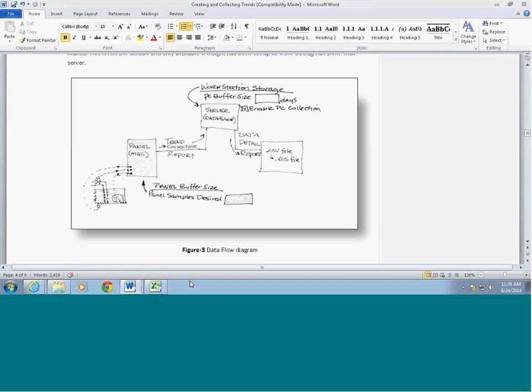That's a little harder. So you have to go to Report Builder, which is that app with access to 1,000 different types of reports. You have to create a new trend data detail report or add it to an existing one. And you have to add all the points that you just set up here. You at least have to select them, each, or a range of points. That's a step that often gets missed.